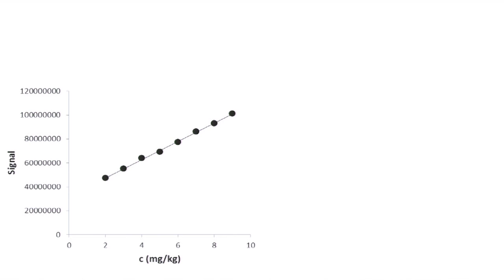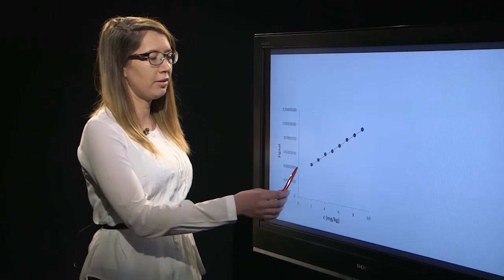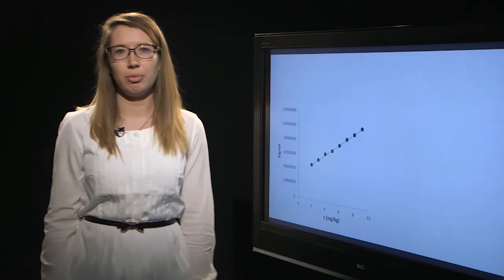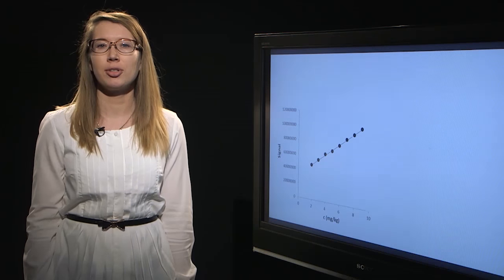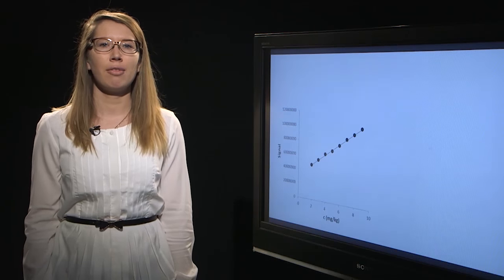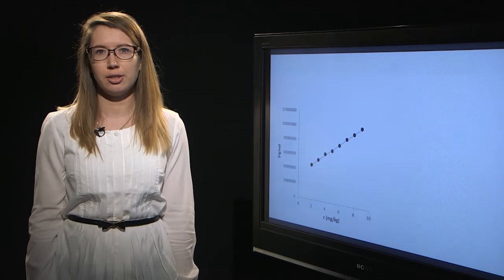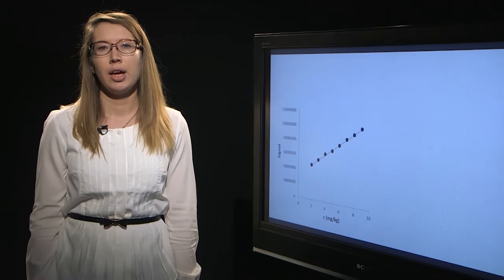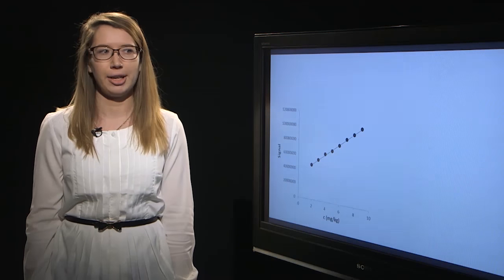Therefore, when using the visual evaluation of linearity, we actually evaluate the random distribution of residuals along the calibration graph. We also evaluate the homoscedasticity. That means that the residuals have to have approximately the same magnitude over the concentration range of interest. Or in other words, the standard deviation of signal should be constant over the observed concentration range.